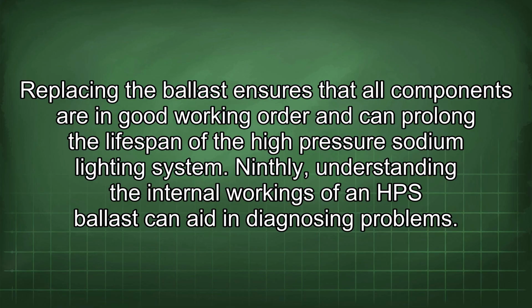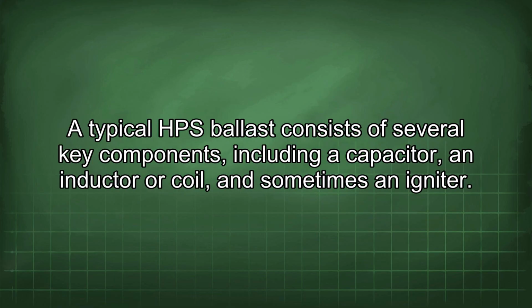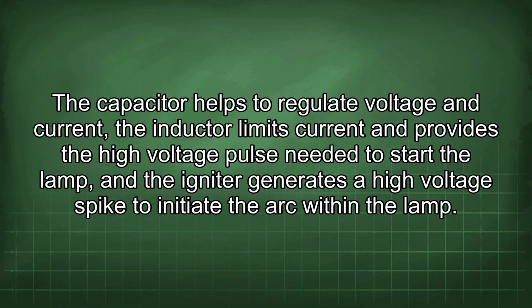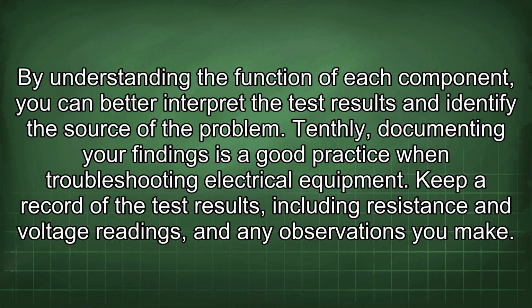Ninthly, understanding the internal workings of an HPS ballast can aid in diagnosing problems. A typical HPS ballast consists of several key components, including a capacitor, an inductor or coil, and sometimes an igniter. The capacitor helps to regulate voltage and current, the inductor limits current and provides the high voltage pulse needed to start the lamp, and the igniter generates a high voltage spike to initiate the arc within the lamp. By understanding the function of each component, you can better interpret the test results and identify the source of the problem.